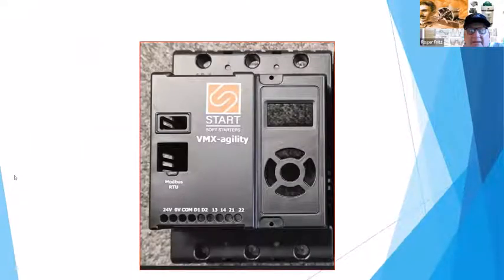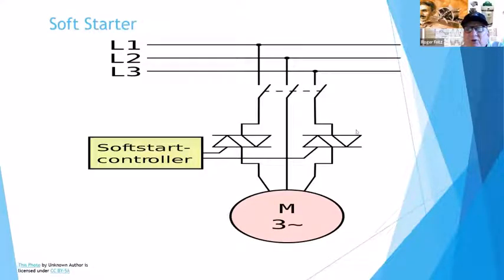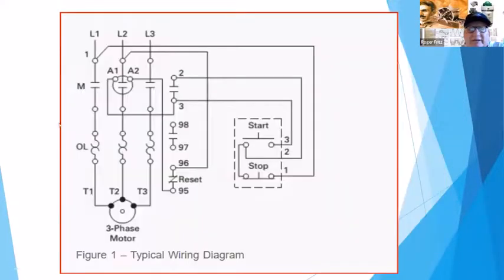And like I said, if you go back to what do I really need? Do I need just to start and stop the motor? Do I need to put just a soft starter in to eliminate that inrush and control water hammer or slow stopping? I think those are the simple and reliable pieces that are in the marketplace, because you don't have much going on to break, and nowadays these SCRs all get shunted out after they're up and running. So they're basically just a standard starter at the end. They're back just running across the line. The motor's happy, getting good, clean power.